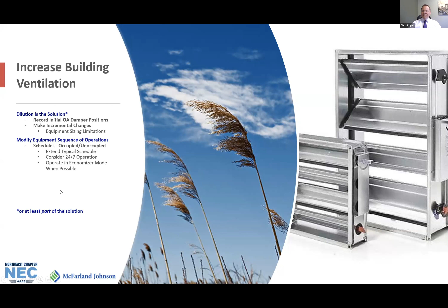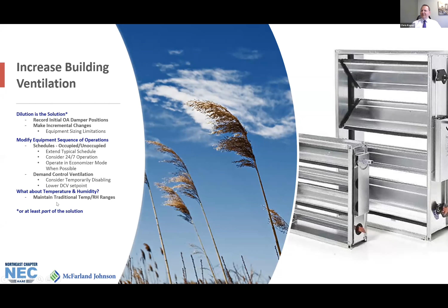Regarding demand control ventilation, this is basically a way to decrease the airflow accordingly as your occupancy in a given space is reduced. It's recommended that during the pandemic you disable demand control ventilation and bring in the outside air that would normally be required during full occupancy of your building. As far as temperature and humidity levels go, I recommend keeping your typical ranges, 68 to 75 degrees with a 30 to 60% relative humidity.